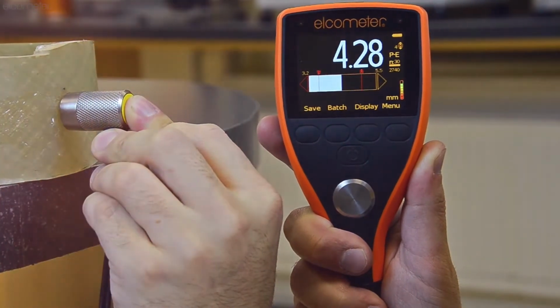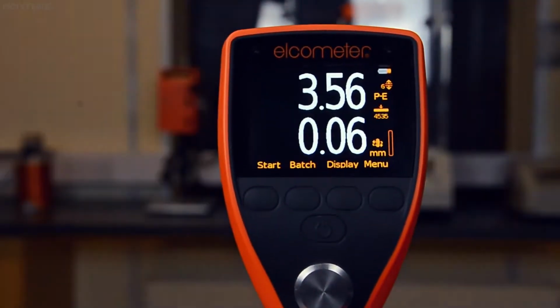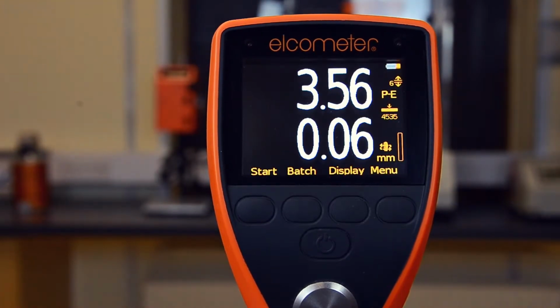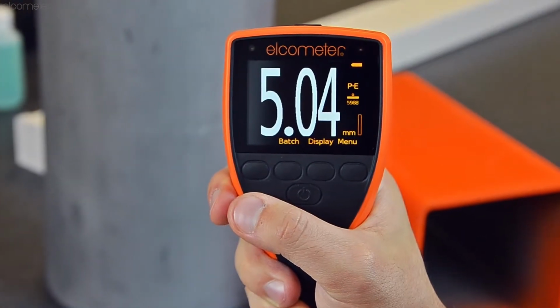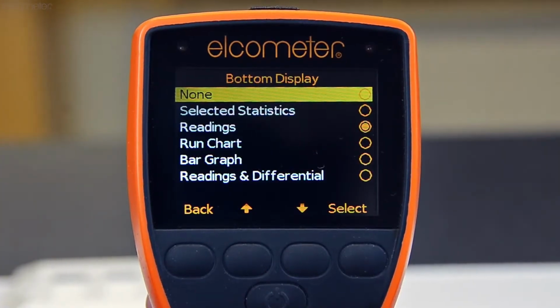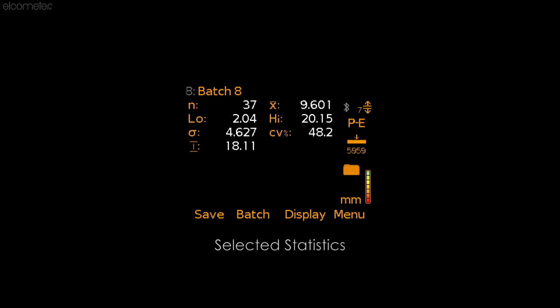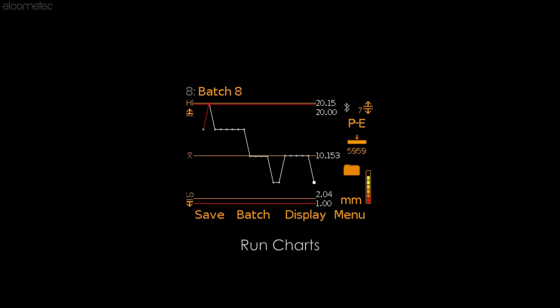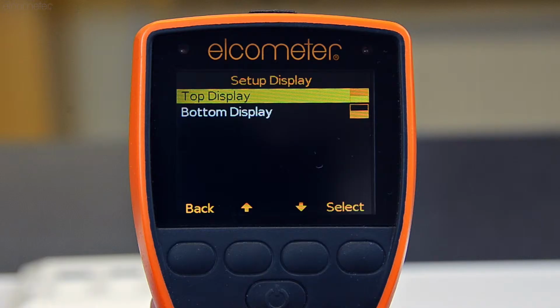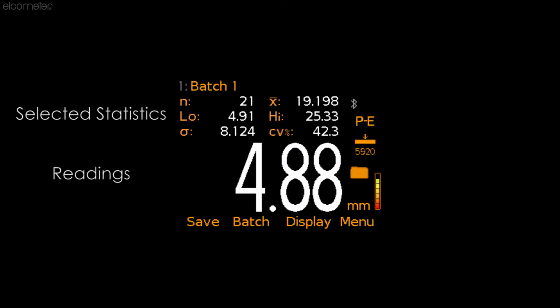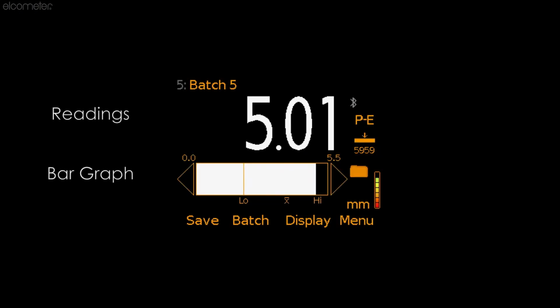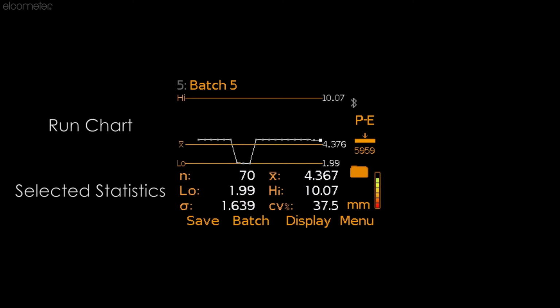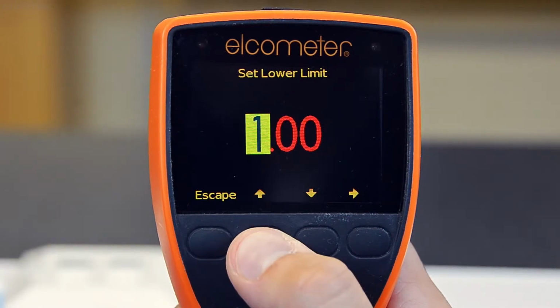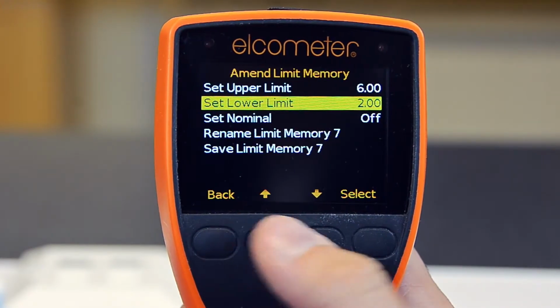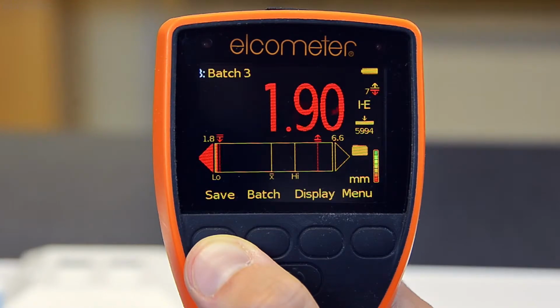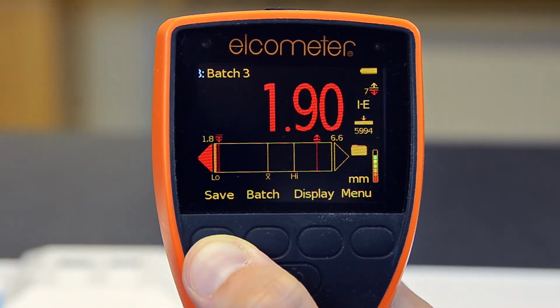With their rugged design and large colour screen with auto brightness, the Elcometer 304 and 307 are ideal for any weather conditions. In addition to displaying the material thickness, these Elcometer ultrasonic gauges have a choice of displays, which include user-selectable statistics, thickness bar graphs, run charts, and much more. The screen is fully customizable, allowing you to choose what information is displayed in the top or bottom half of the LCD, so the information that you need is on screen at all times. Once you have defined the high and low limits, whenever a reading exceeds the range, the gauges give you an audio and visual warning, clearly highlighting any problem areas.